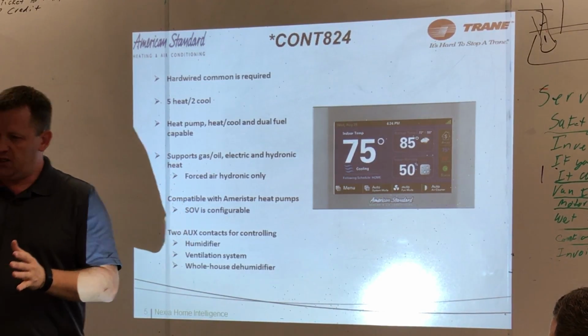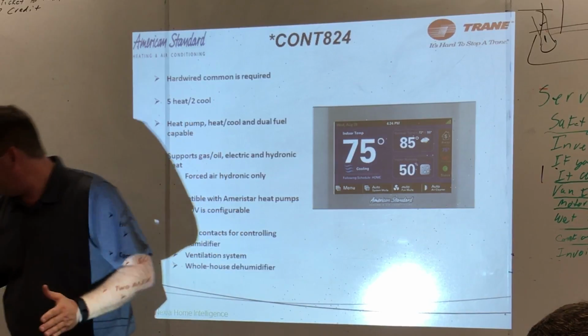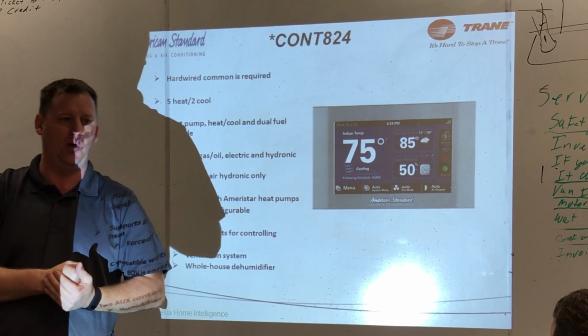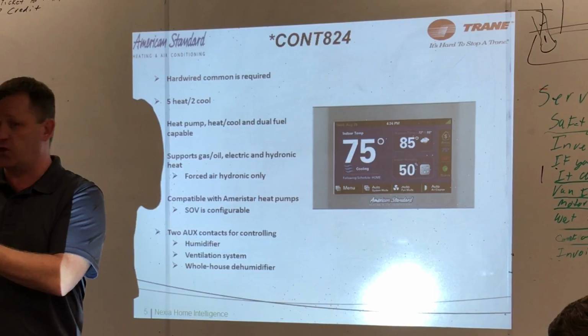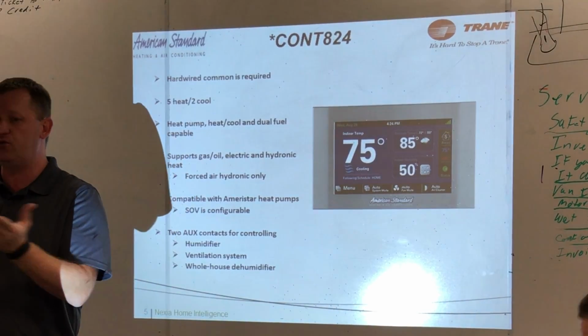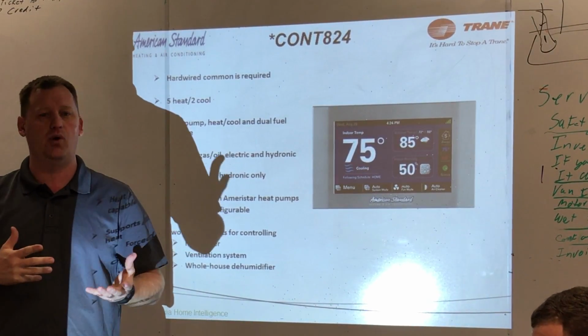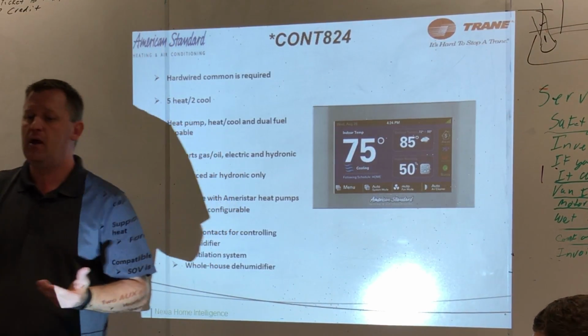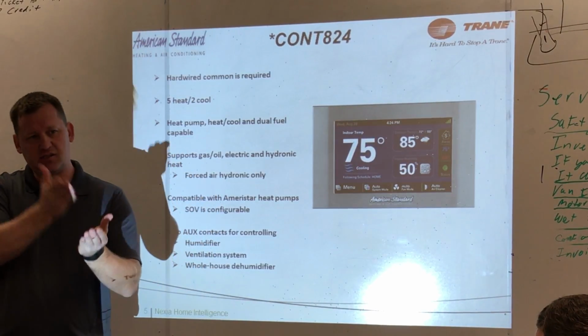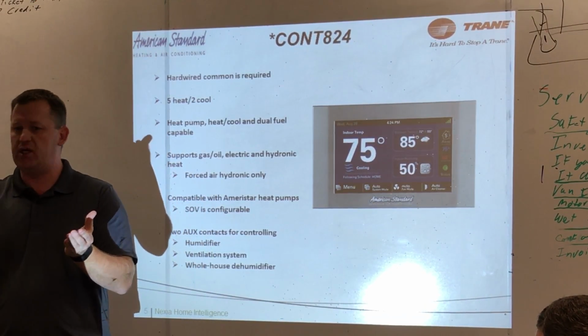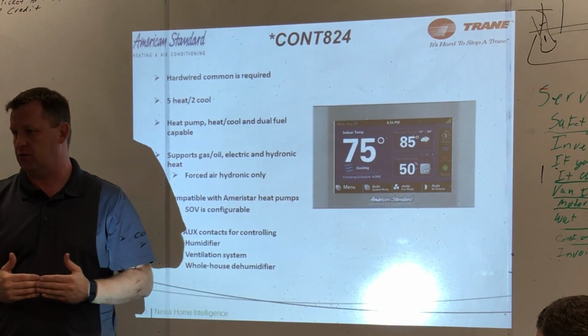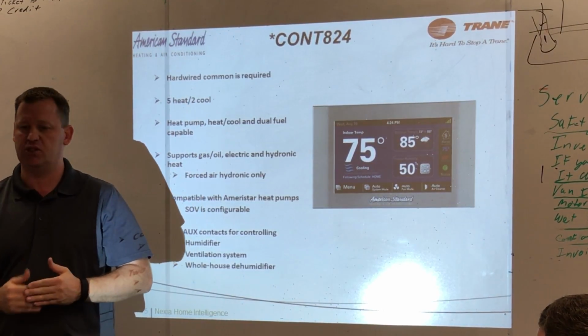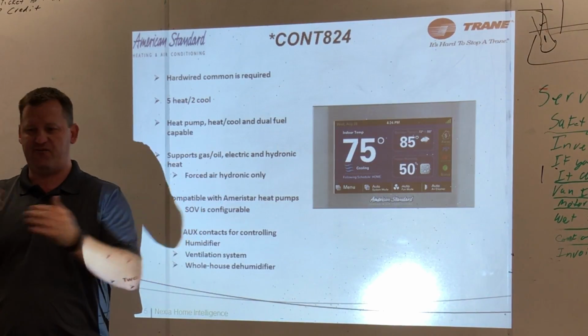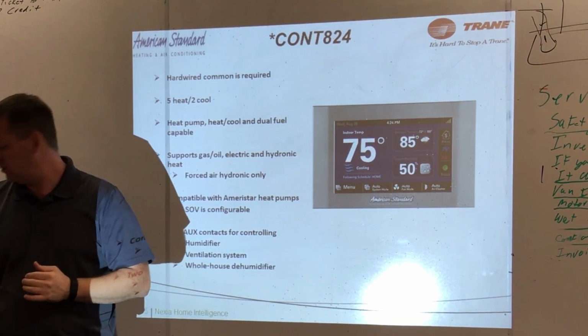What that means is efficiency and comfort, because if we bring on all 15K at once we risk overheating the house. With a Honeywell stat we sometimes overshoot when the auxiliary heat comes on. With this, it stages each set of auxiliary heat so we overshoot less often, and we're not dimming the lights when all 15K kicks on at once, which can create a homeowner complaint.